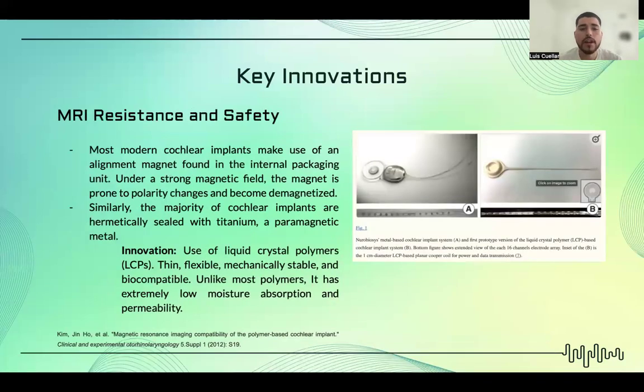And finally, when talking about MRI resistance and safety, a lot of the issue comes from two parts. It comes from the magnet in the internal unit and also the titanium package of the hermetic sealing. As far as the magnet itself, it's a problem because it can become demagnetized and it can even suffer a change in polarity through the strong magnetic pull, the magnetic field that is created by the MRI machine.